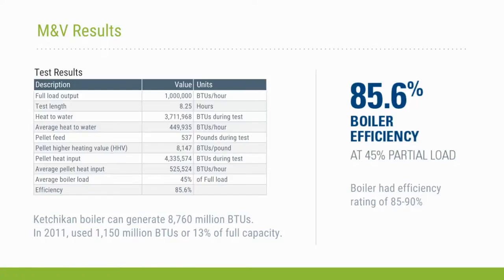So after the testing, we concluded that the boiler was running right about 85%, a little bit better than that, which is within the claims. I think that it was also better than what we had expected, because during the testing period, the boiler was only running really at 45% of its rated load. And boiler systems are designed to run at full load, and their efficiency tends to drop off as you drop load. So running at 45% and still achieving 85% efficiency was, I think, a success. I think if it had been running at 80, 90, or 100%, you'd see even better boiler efficiency than that.